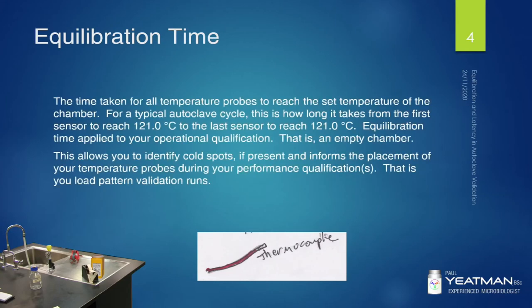So let's get into equilibration time. This is the time taken for all temperature probes to reach the set temperature of the chamber — so for a typical autoclave cycle, that's how long it takes to reach the 121 degrees Celsius required for your kill cycle. This applies during your operational qualification, so when the autoclave is empty. That allows you to identify cold spots, and if they're present it informs the placement of your temperature probes during your performance qualification.